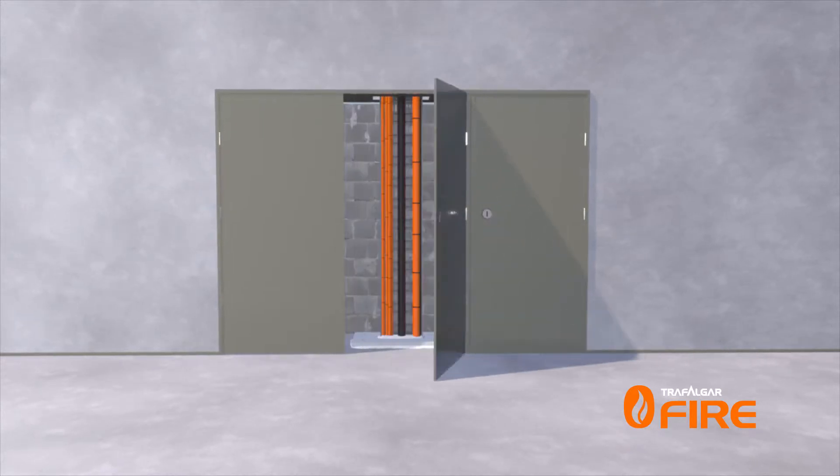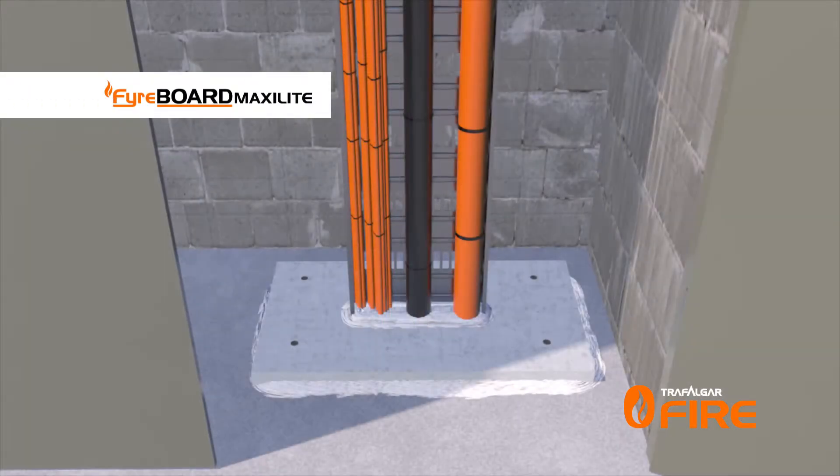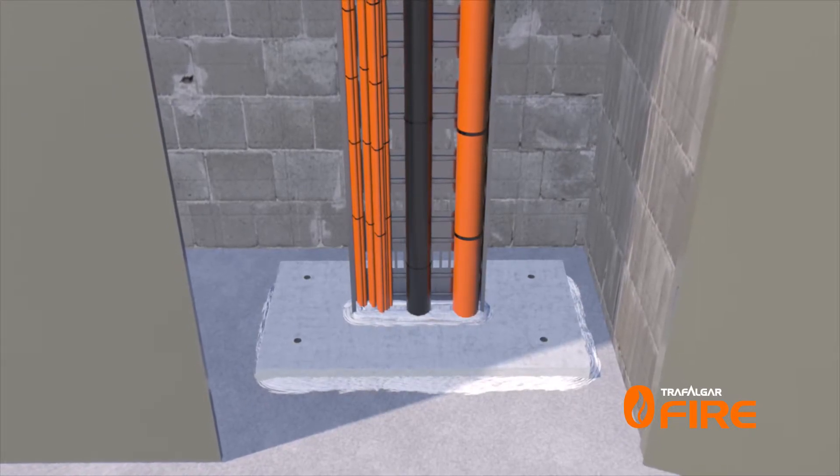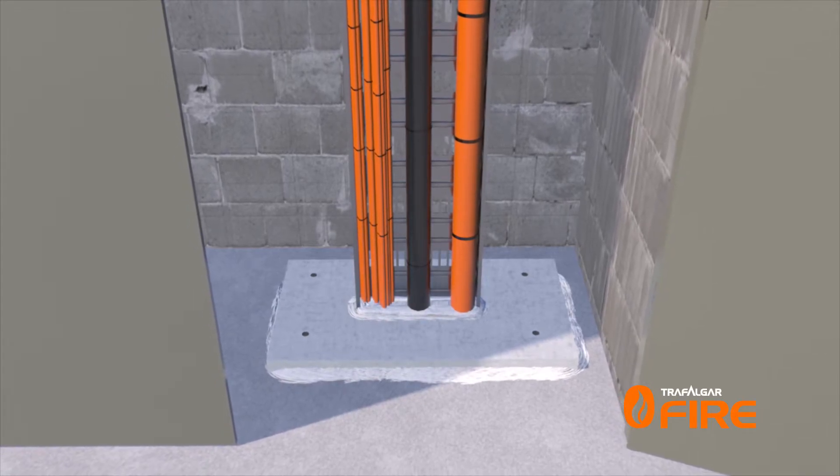In this installation video, the penetration has been sealed with FyreBOARD MaxiLite to provide two hours of integrity performance. However, as the cable surfaces will transmit heat through the penetration, it will need to be wrapped to limit the heat rise.